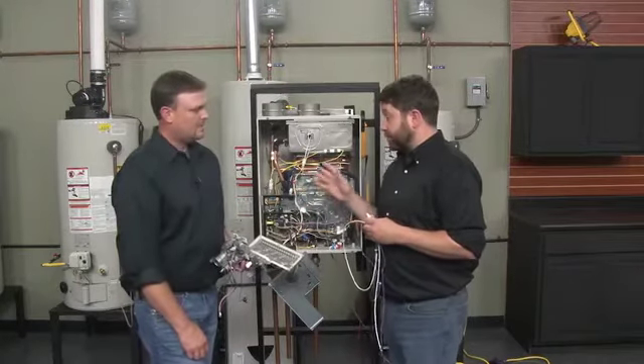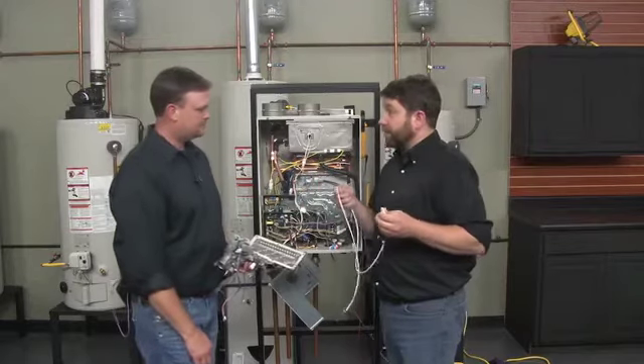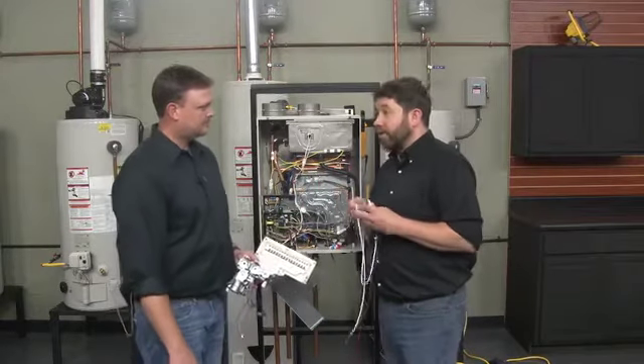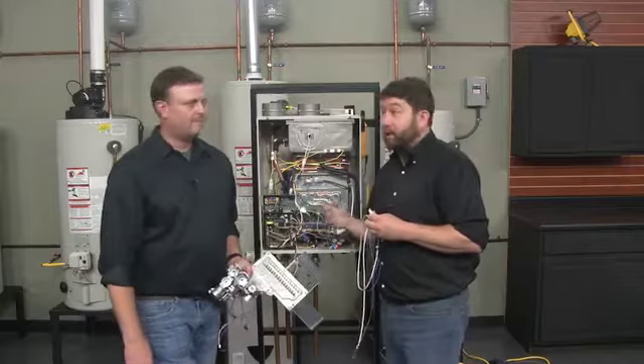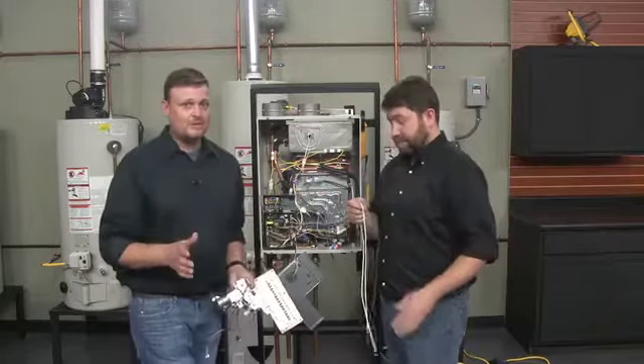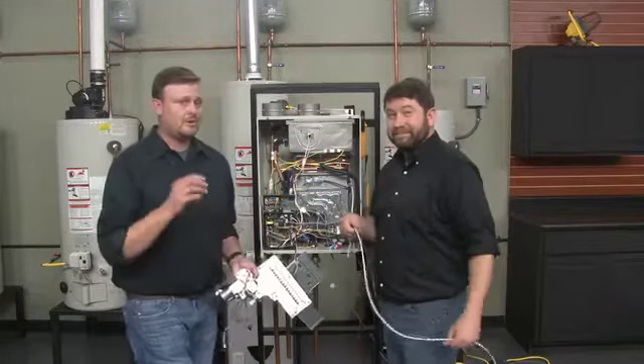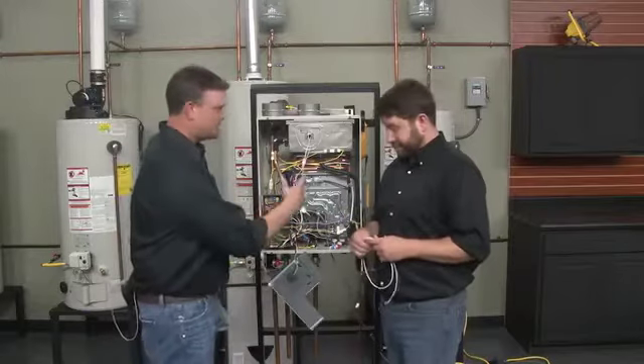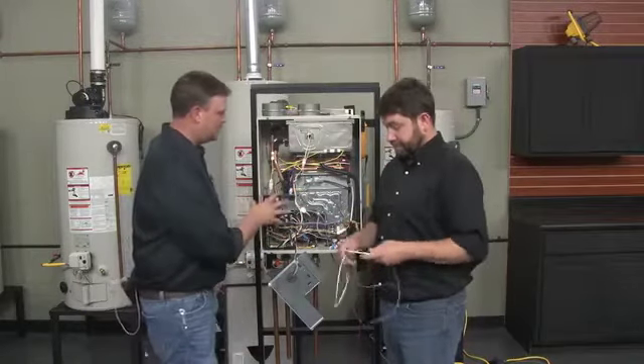And correct the issues. Now, if there's nothing wrong with the heat exchanger and we're going to put this back in, it still has to be all the way out because we have to wrap it back around in the same routing. So make sure that you take a picture of it if you pull it out and look at it, because it does wrap around the backside uniquely.